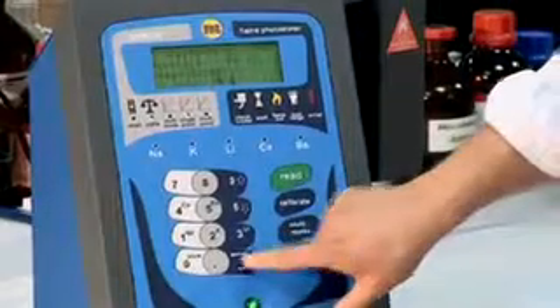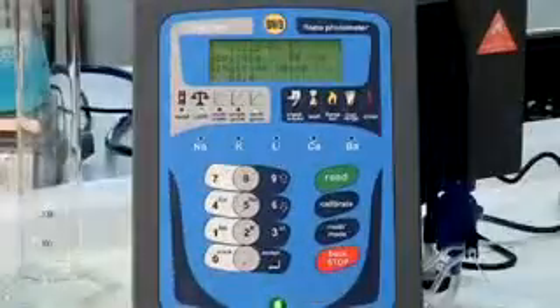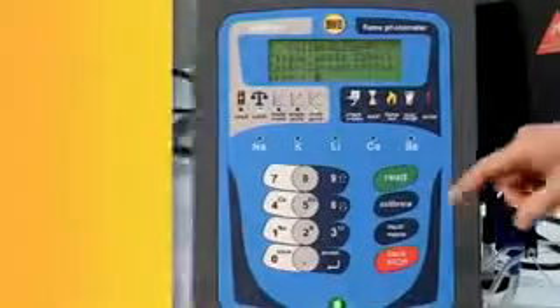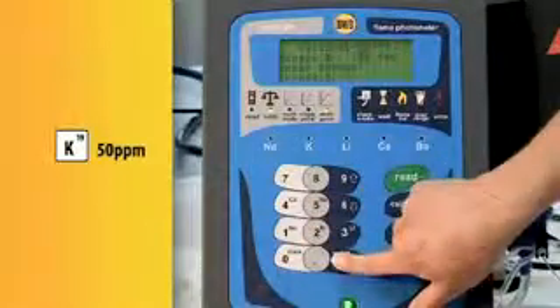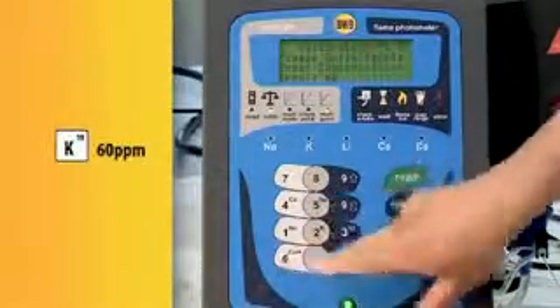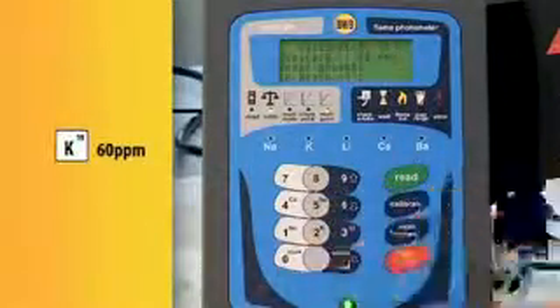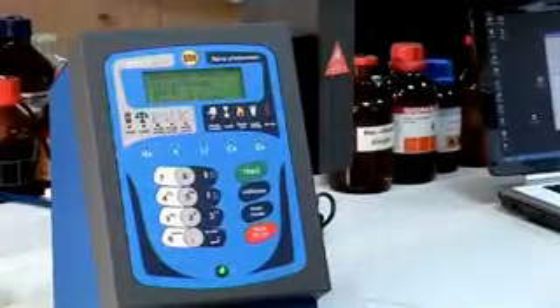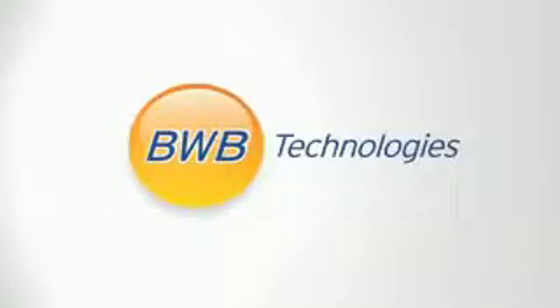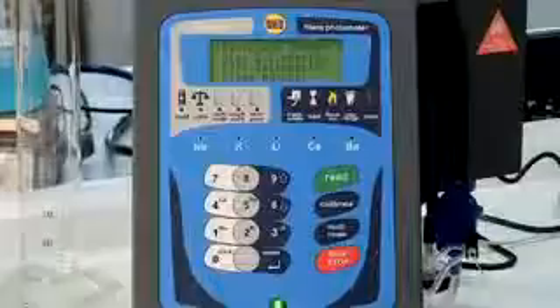When the blank is ready, we are prompted to enter the concentration of the standard. Key in 50 on the Bwb Xp. Press Accept. Start aspirating the 50 ppm potassium standard. Press Accept again and the calibration point will be determined. Again, we can follow along with the FP PC as the calibration progresses. When the calibration is finished, tick on the Retrieve Calibration box and the FP PC will now be ready to report potassium readings.